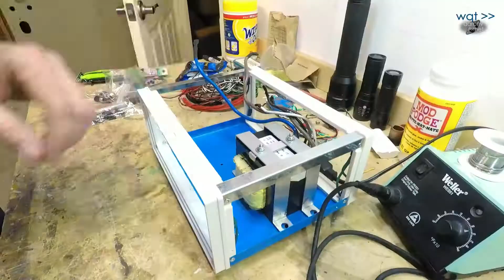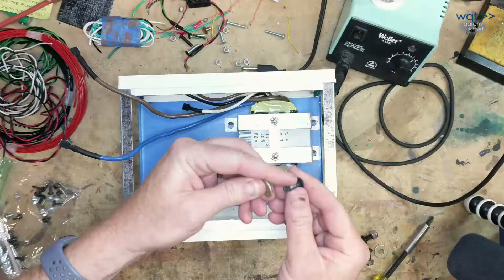Okay, first up we've got to get this transformer mounted in here. I've got these bolts, and I'm going to go ahead and put three of them in right away, saving the fourth one until we get a proper ground terminal made that comes back to the outlet. Since this base metal is so thin, I'm just going to put these grade 8 washers on both sides of the connection.